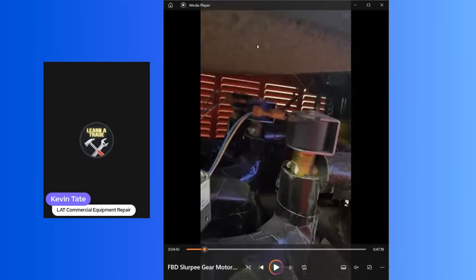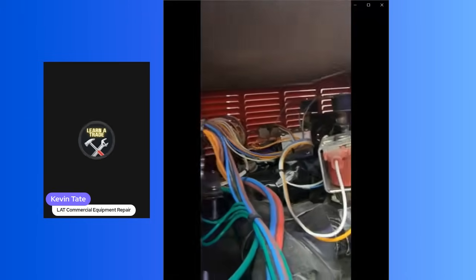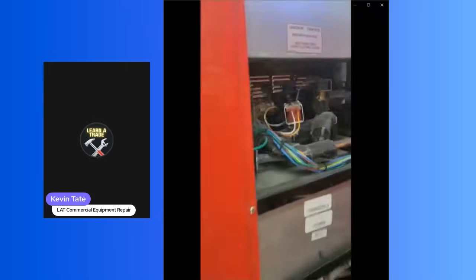If you take a look up here, you see how dirty that filter, that air filter, is. I'm going to have to remove that filter, clean it out, and then I'll also clean out that condenser coil just to make sure everything's cleaned out before I wrap it up. That screen is real dirty - you can see it all coming out there.